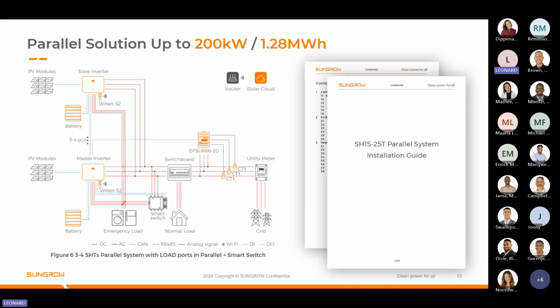This is just a quick introduction to the paralleling of our 25 and 15T inverters. Currently, this is a basic SLD of how we will do the paralleling. So we will have a smart switch in the middle just to make sure that the system goes into bypass when the inverter synchronizes back to grid again. This will just make sure that the system is more reliable.